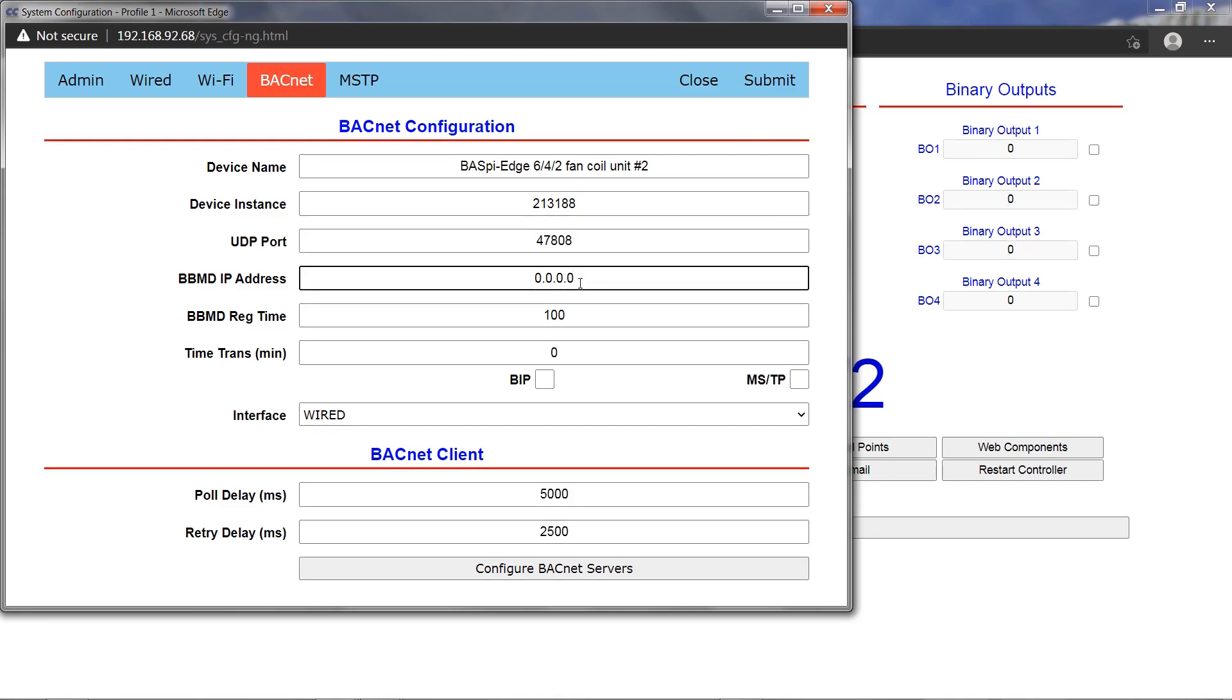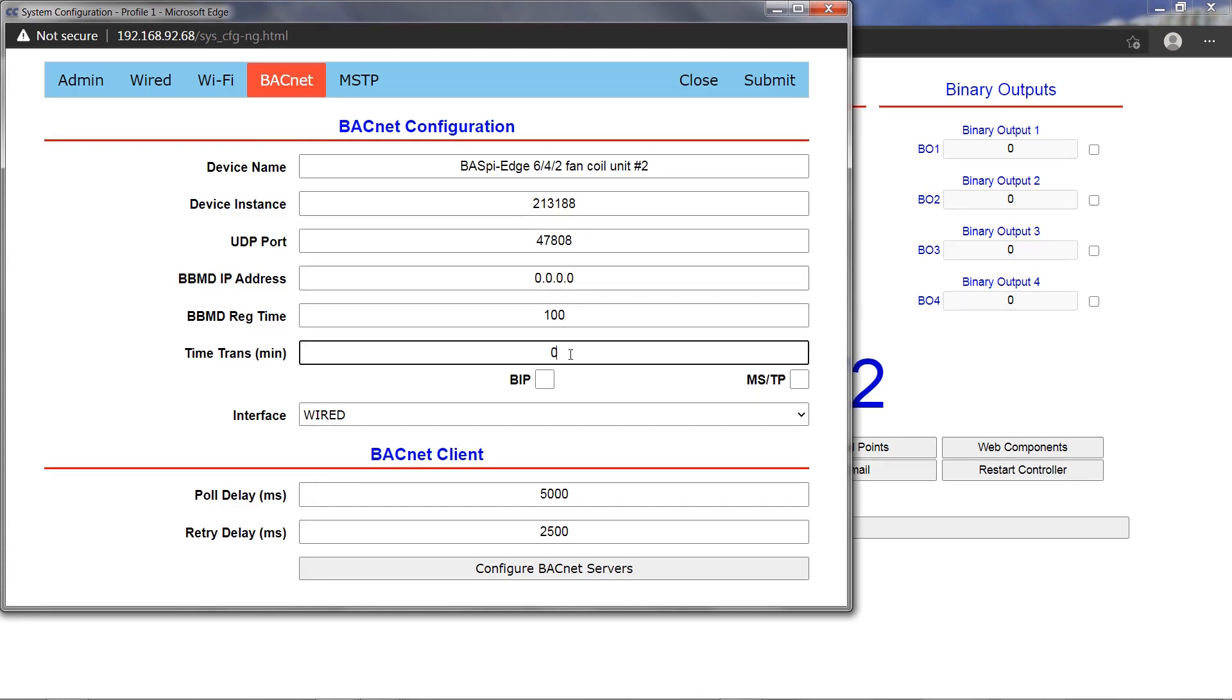A BACnet device with BBMD capability, such as a Contemporary Controls BASrouter or BASrouter LX, is required to be installed and configured on the network for the BACnet to be discoverable from another IP subnet.